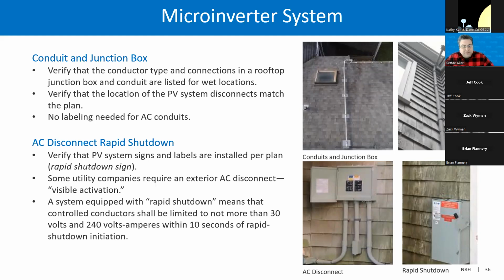Some utility companies require an external AC disconnect for visible activation. In that case, the rapid shutdown label must be installed per plan. A system equipped with rapid shutdown means that the controlled conductors shall be limited to not more than 30 volts and 240 volt-amperes within 10 seconds of rapid shutdown initiation.